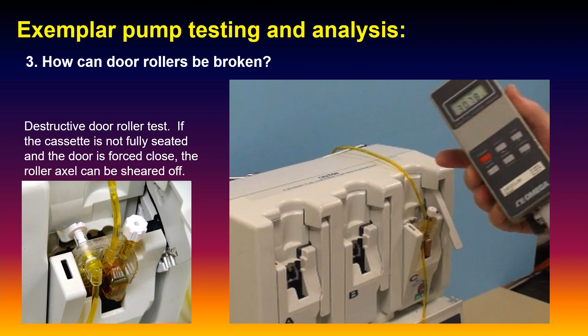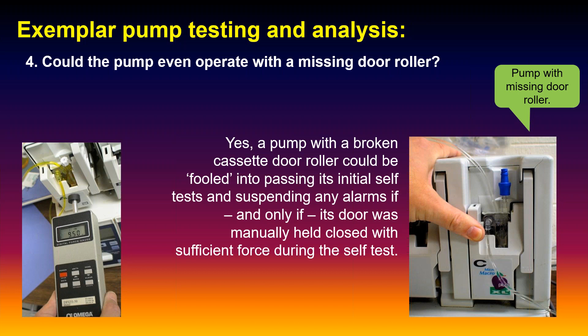The other question I had was, could you even operate this thing with a broken door roller? I found this out on a fluke, I had no preconceived sense that I could do this. I was just holding the pump door closed, turned it on, and it goes through its self-test for about 10 seconds. You can feel the pump, the pistons going in there, you're getting feedback. I held the door closed, and sure enough, I could make the thing run.